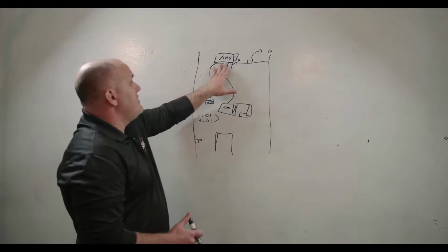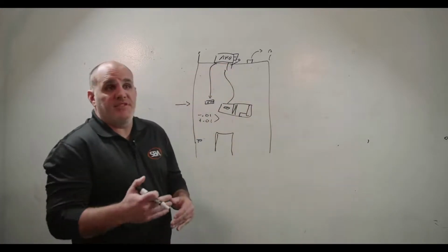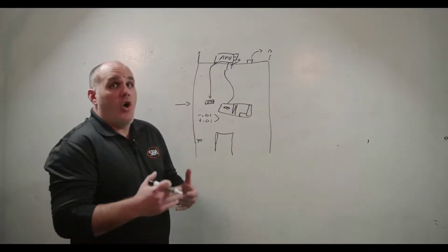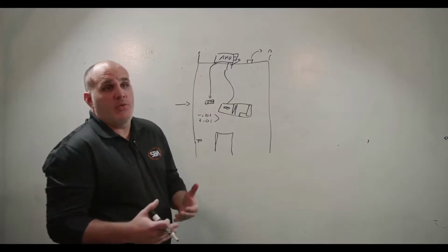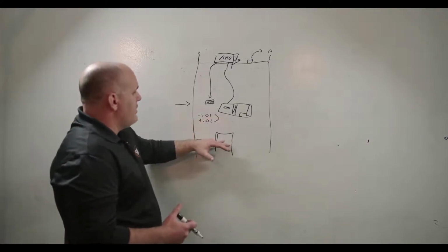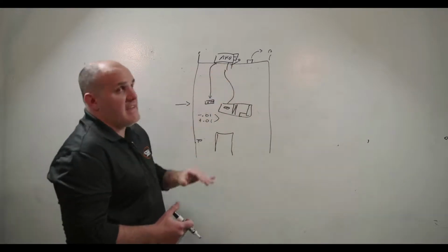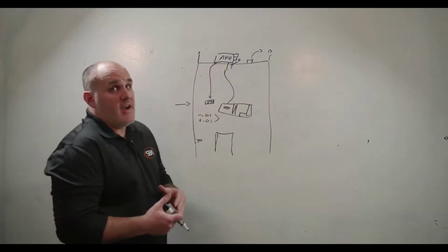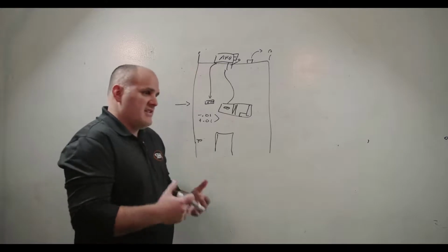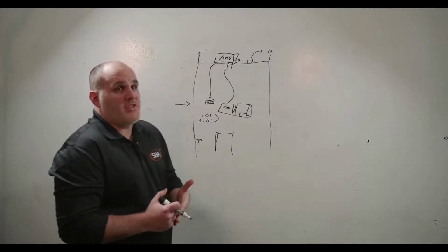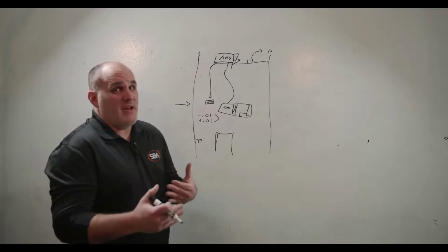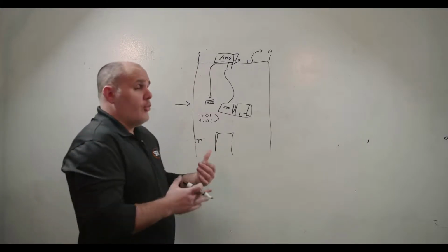So we really need to be cognizant that our pressure set points for building static pressure are actually quite low. Now, when we get into the air handler, you can see up to 4 inches water column on a really high pressure air handler. So just be aware that while it is pretty low in the building, we can get potentially high on the air handler side. And then obviously when we get into the hydronic space, we're commonly sitting somewhere between 20 to 50 PSI on the hydronic side for water.